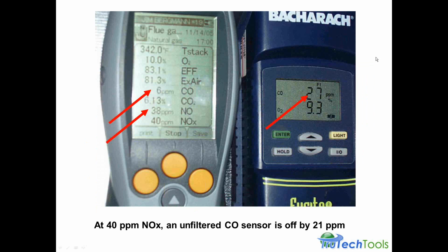Here's an example, and it's using some older equipment, but this does drive home the point. This was an analyzer that did not have a NOx filter built into it, or an external NOx filter applied. It showed 27 parts per million CO. And here's an analyzer whose CO sensor was filtered for NOx and also happened to be measuring NOx. So you can see at about 40 parts per million NOx, it impacted the CO reading on this unfiltered CO meter and gave it an extra 21 parts per million. So actually 6 was present, but this one showed 27. And that extra 21 came from those 40 ppm of NOx, where we talked about 40 to 50%. In this case, almost exactly 50% of the NOx was read through by this CO sensor as CO.